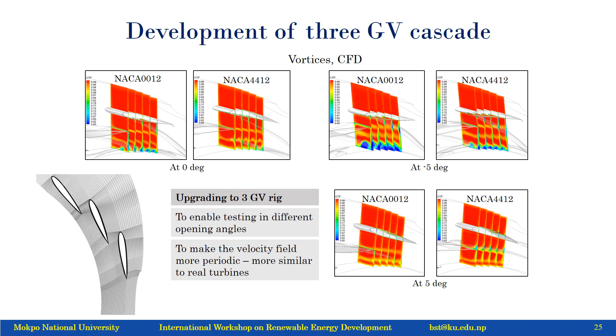So my first conclusion is Francis turbines designed with standard methods are not suitable for sediment laden projects. It's due to the inherent velocity peaks around guide vanes and at the runner outlet that make Francis turbines very bad with sediments. And we found that the design of guide vanes plays a very important role, particularly the profile. The symmetric NACA profile was found not to be suitable for sediment laden projects because of the high pressure difference towards the trailing edge, and this induced erosion in turbine components as well.